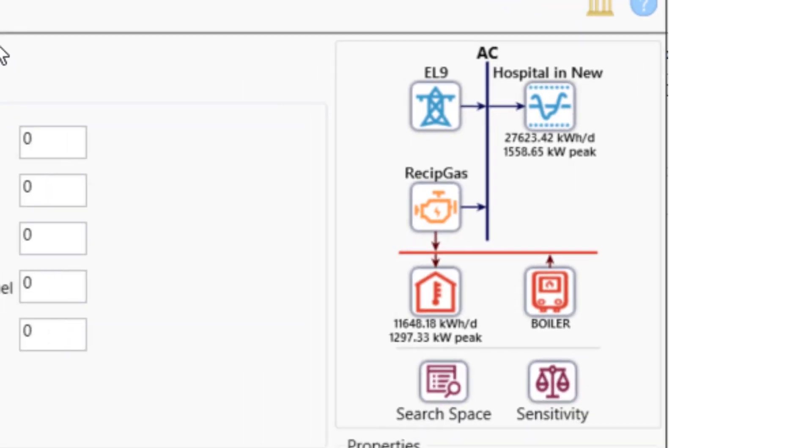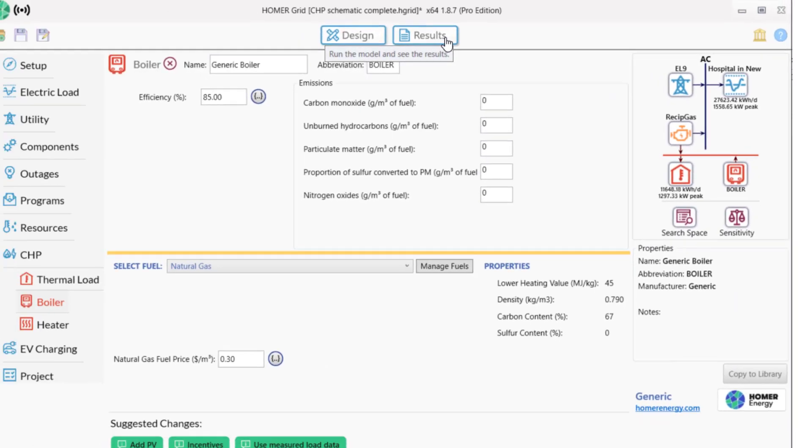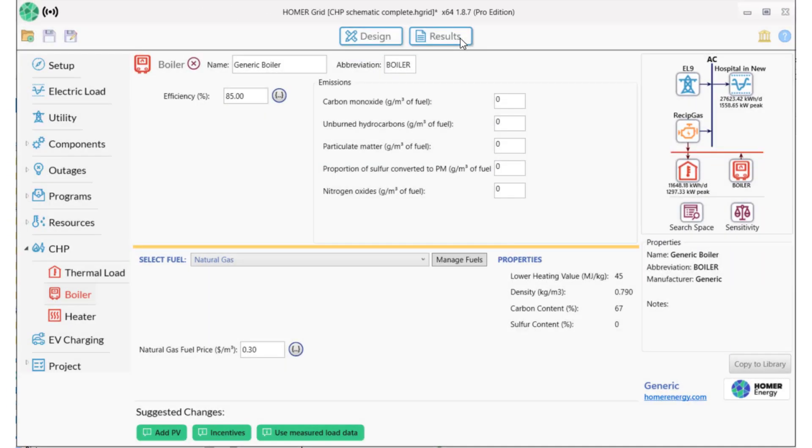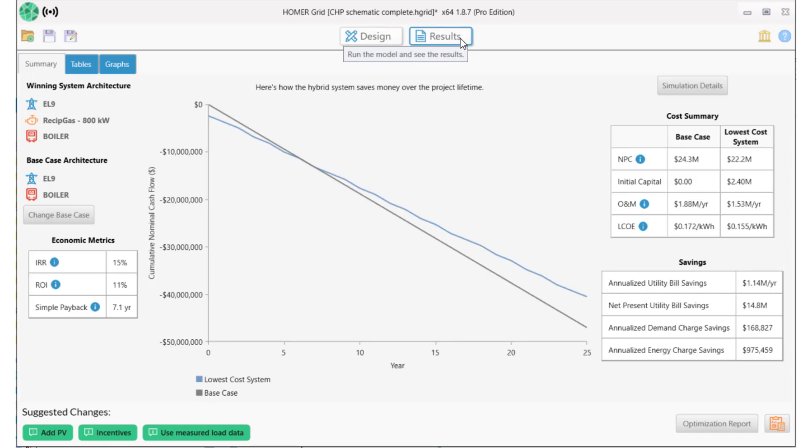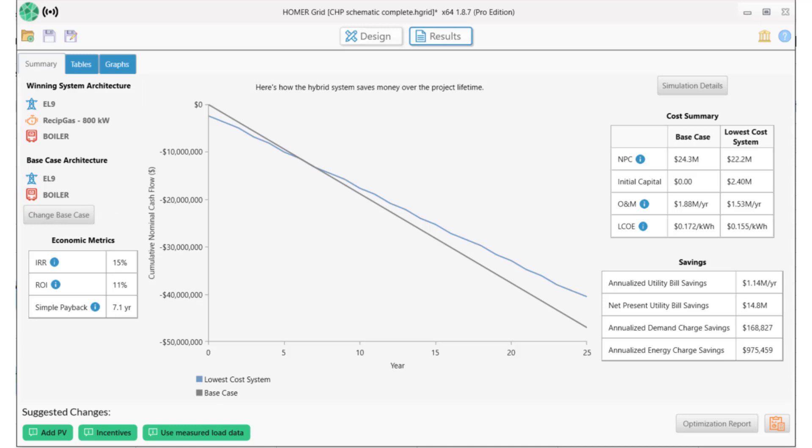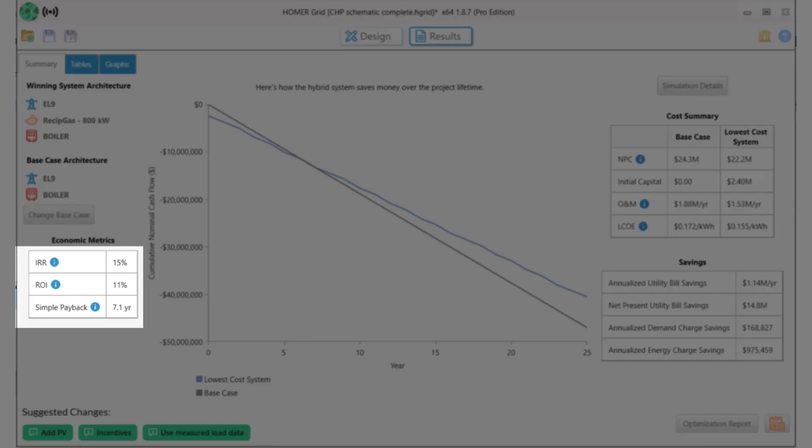The first thing to note is that the CHP system with the reciprocating generator is the best system economically. The 800 kilowatt generator was the winning system. It had the lowest overall net cost. This project has an internal rate of return of 15 percent, an 11 percent return on investment, and a simple payback of seven years.